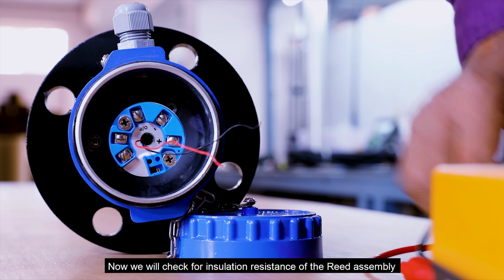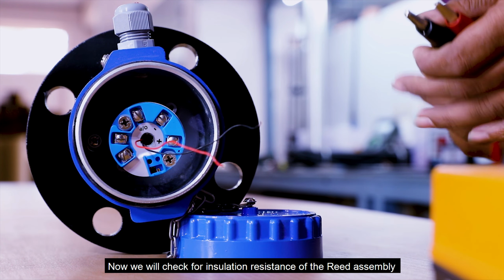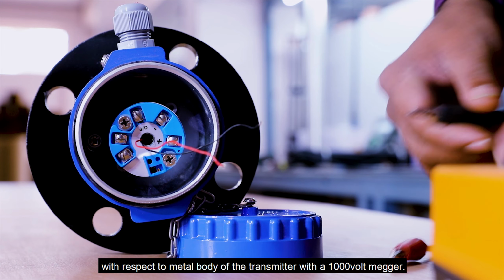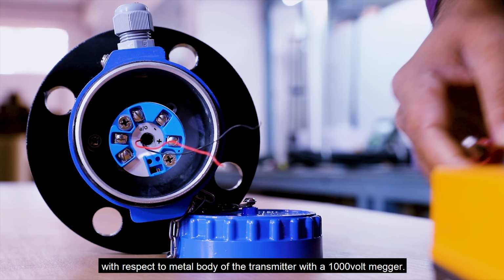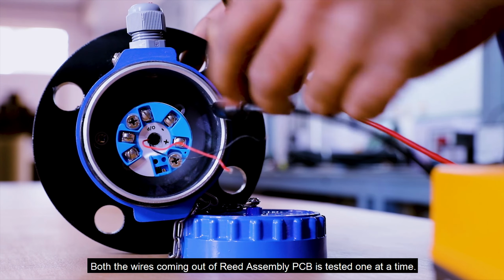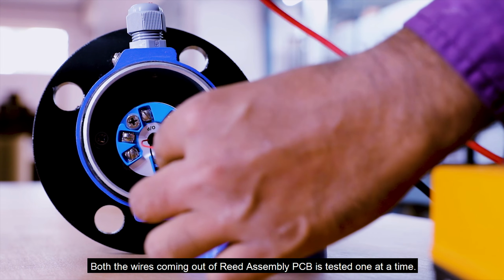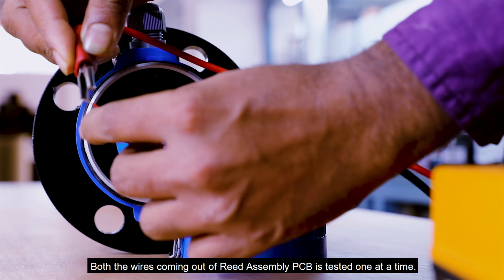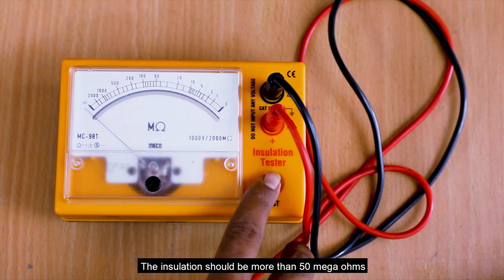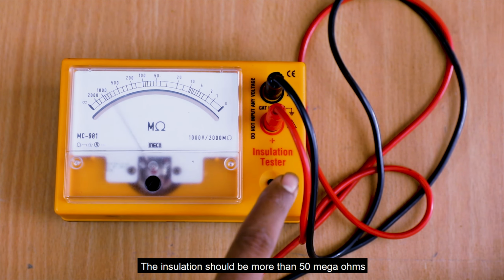Now we will check the insulation resistance of the reed assembly with respect to the metal body of the transmitter with a 1000 volt megger. Both the wires coming out of the reed assembly PCB are tested one at a time. The insulation should be more than 50 mega ohms.